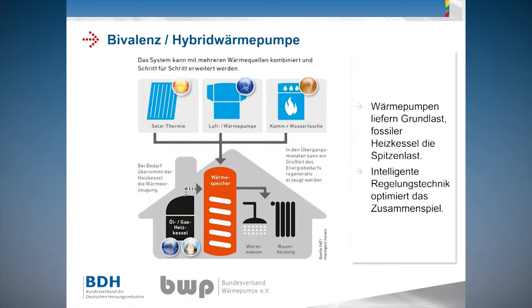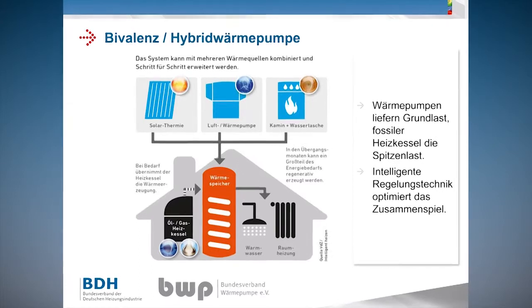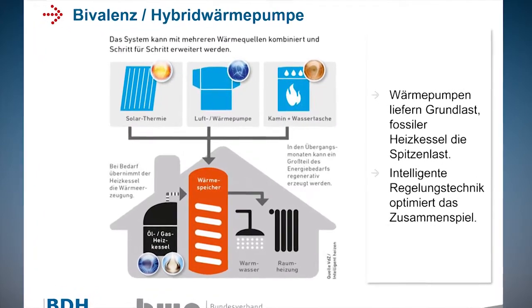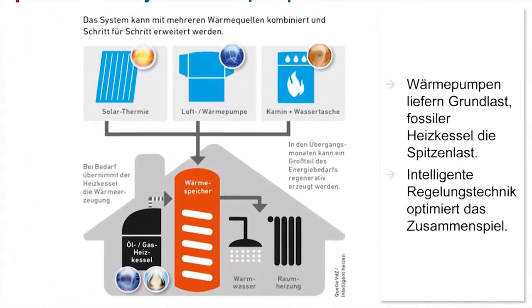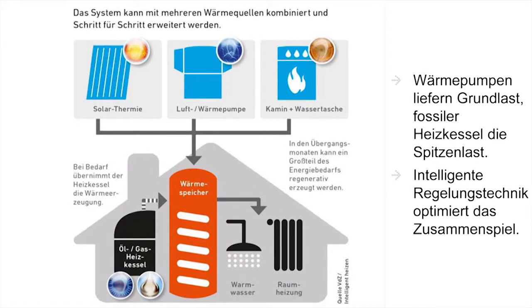Therefore bivalence, as it's known in the heating business: when you don't reach a corresponding temperature level, you combine two technologies, normally a heat pump and a boiler. Or, in the upper range, you design the heat pump conventionally to cover 100%, which makes the station quite expensive and large. So the solution is a bivalent or hybrid station, meaning 90% is covered by the heat pump and the rest is added on top in a peak situation, which lets you avoid that intensive, expensive setup.